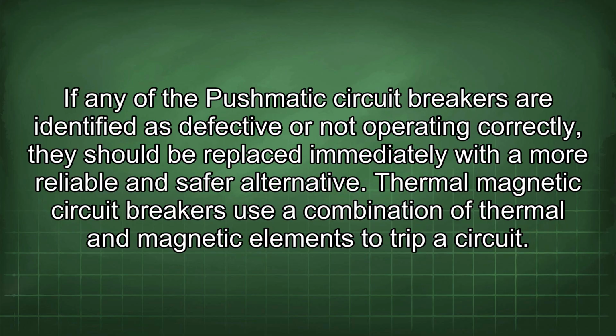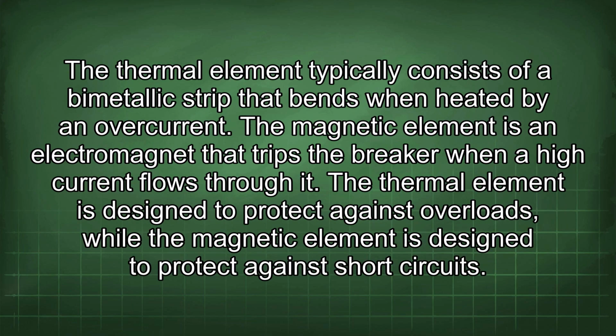Thermal magnetic circuit breakers use a combination of thermal and magnetic elements to trip a circuit. The thermal element typically consists of a bimetallic strip that bends when heated by an overcurrent. The magnetic element is an electromagnet that trips the breaker when a high current flows through it. The thermal element is designed to protect against overloads, while the magnetic element is designed to protect against short circuits.